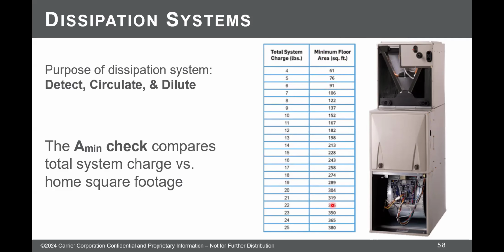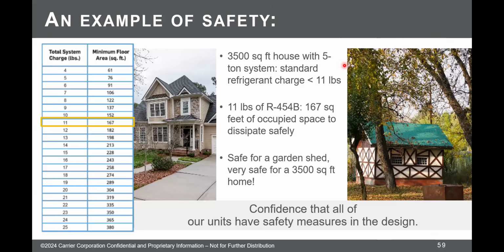Technically, it's cubic foot, but nobody wants to start calculating cubic feet of a space because people aren't good with math, at least not in HVAC. So they made this square footage chart, assuming that every ceiling is 7.2 feet or smaller, which 7.2 feet is pretty small. So for example, if I take this chart and I go, okay, I got 11 pounds of charge in this system, it cannot service an area of a building or home that is less than 167 square feet. That's not going to be hard to do. 167 square feet is a 16 by 10 room. This is a super small building.